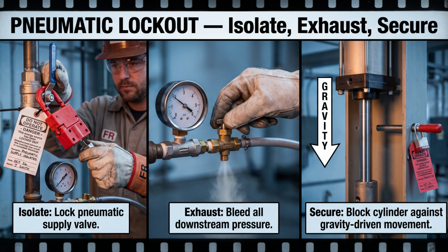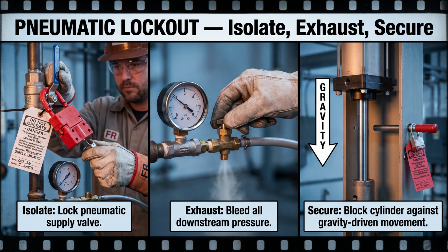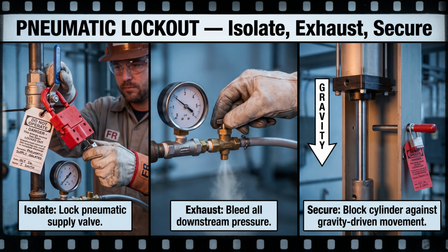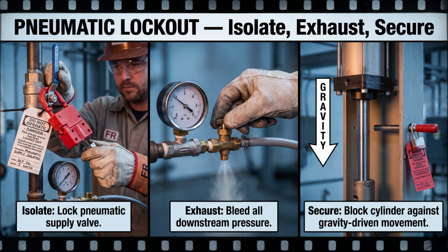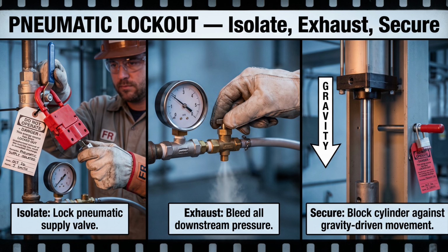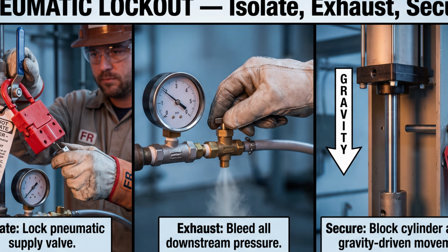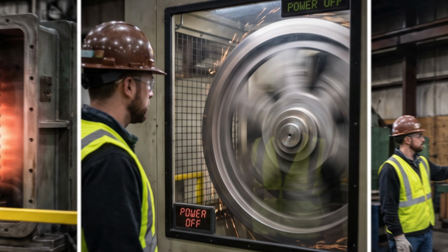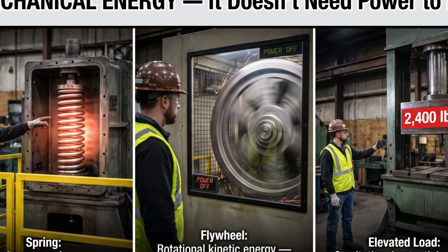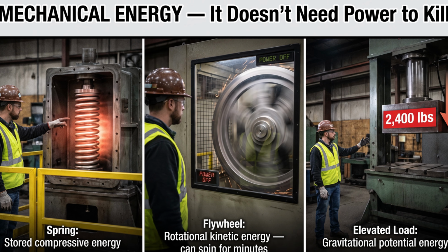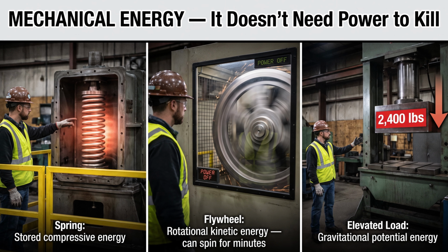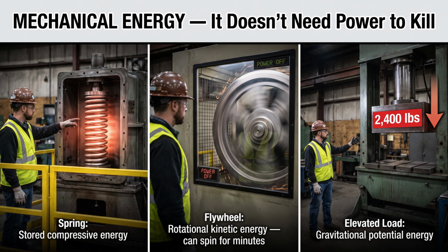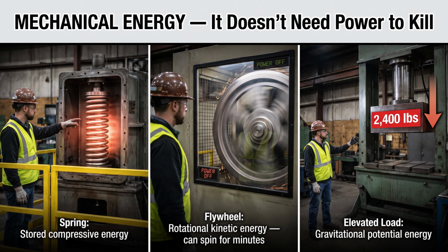Lock a pneumatic ball valve or air supply valve using a valve lockout device and your padlock. Then, exhaust downstream pressure through a manual bleed valve until confirmed at zero by a pressure gauge. Finally, for pneumatic cylinders, gravity can still move a cylinder after pressure is exhausted if a load is involved. Mechanically block any cylinder that supports a load. Mechanical energy includes stored energy in springs, flywheels, counterweights, elevated components, and anything held against gravity. A loaded spring can release fast enough to sever a finger or fracture bone.